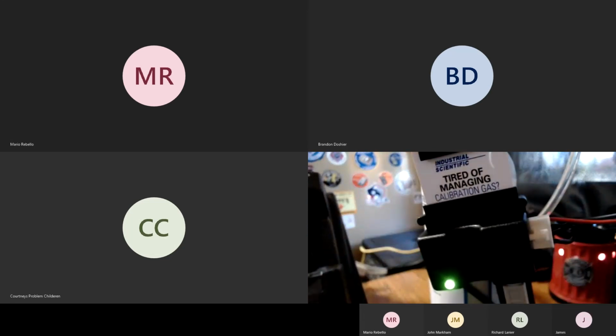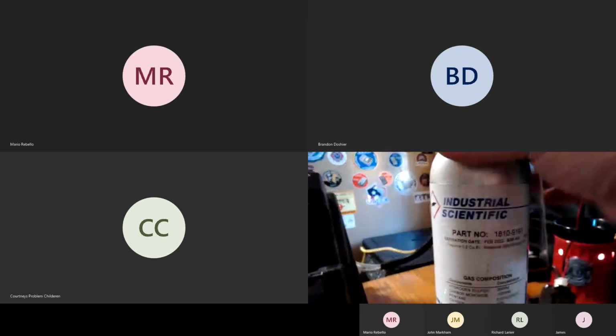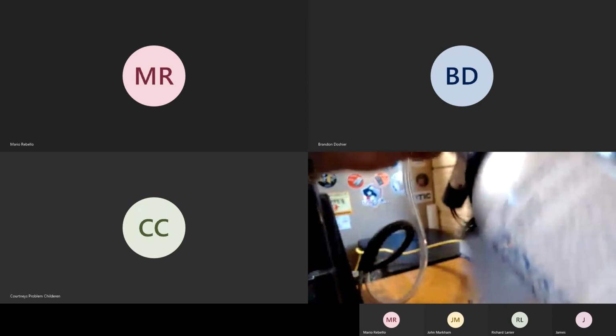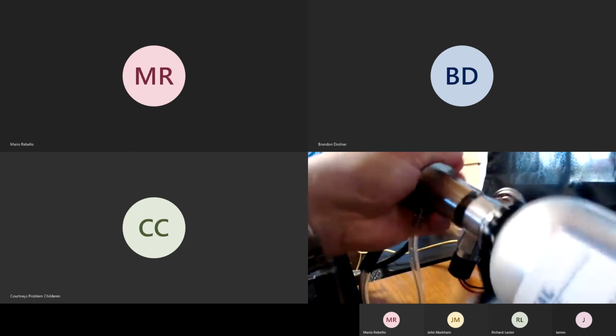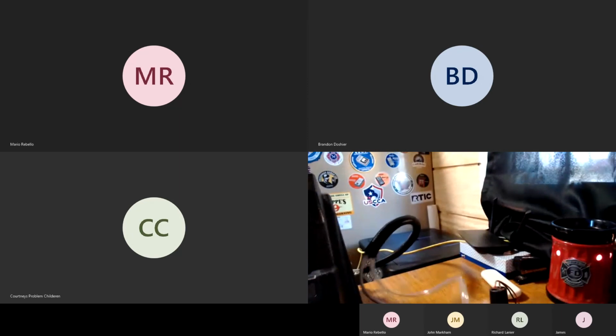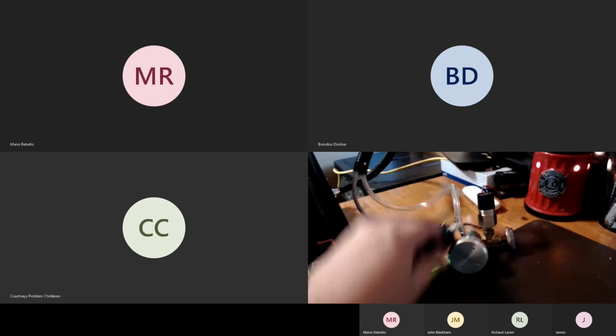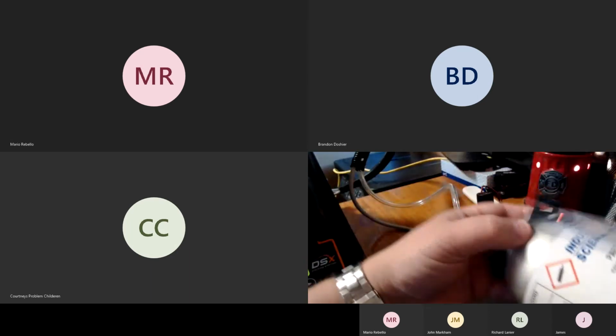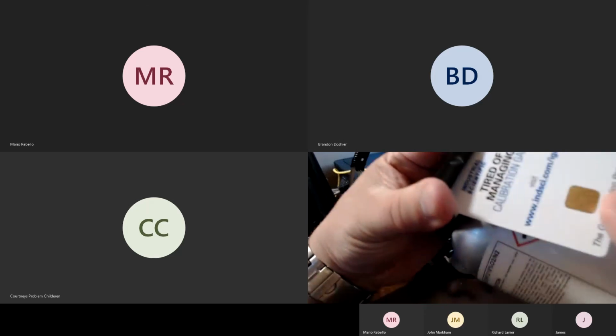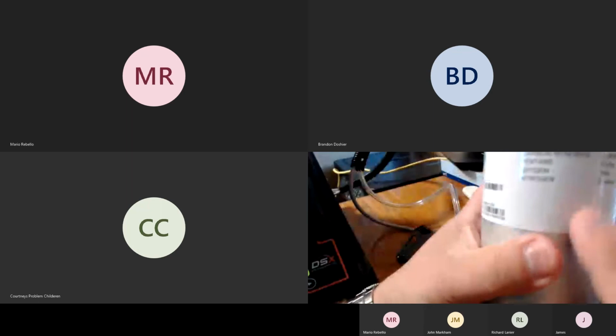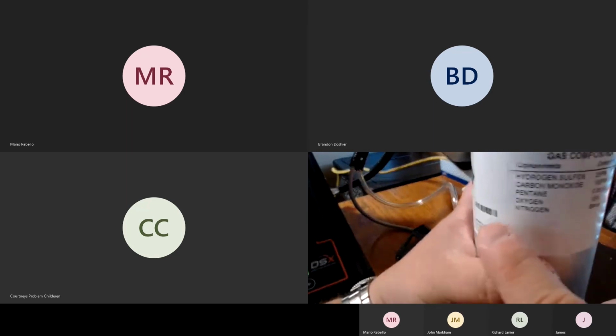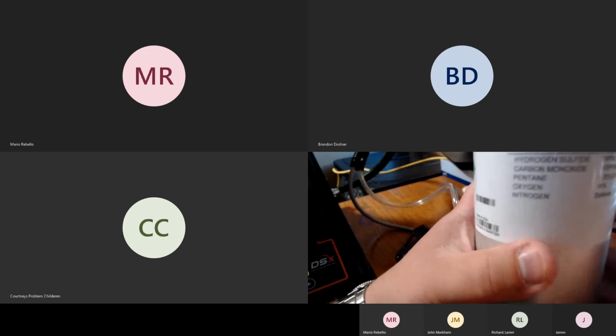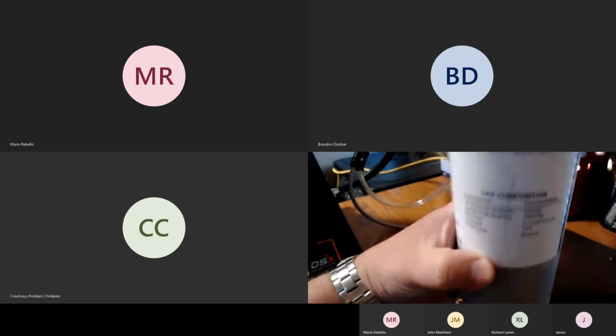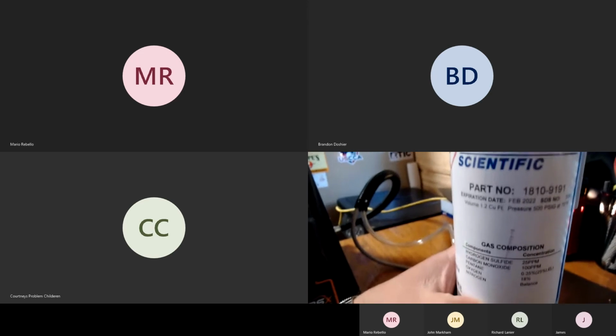Now when you're connecting up the gas bottles, there is actually a way that you need to do this. So I'm going to disconnect all this and show you how that goes, because you have to connect it in a certain way, or else the docking station will think that you've connected up an empty bottle of gas. So I have my regulator, my card reader, and my bottle of gas. The bottle has this little card on there. The card has this little gold chip, which gives it all the information that is on the bottle's label: the concentrations, what gases it is, the expiration, the lot number, everything. That's all programmed onto the chip itself.